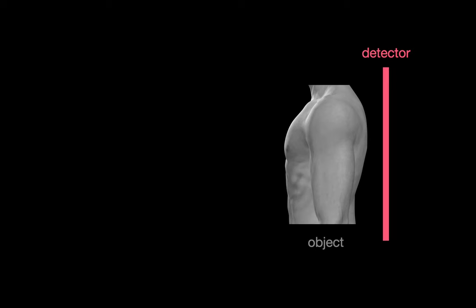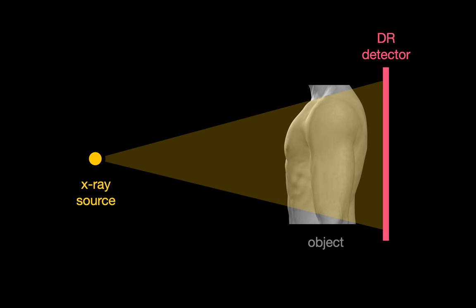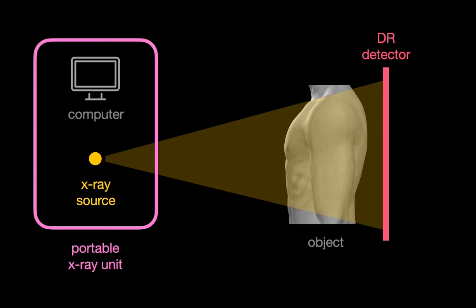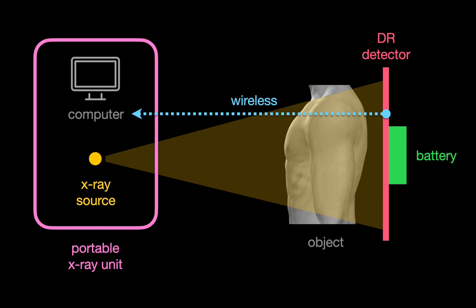Most modern portable x-ray systems are composed of a DR detector panel, an x-ray tube, and a computer. The DR detector panel is powered by a rechargeable battery and can transfer x-ray images wirelessly to the computer, which itself can upload that portable chest x-ray image to the hospital-wide PACS system via Wi-Fi so that anyone in the hospital can immediately see the patient's portable chest x-ray image on their computer.